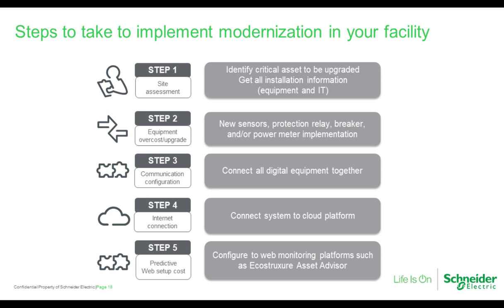Some of the steps to take to implement modernization. When we're looking at implementing thermal sensors, protective relay, breaker, and power meters, there are 5 steps that can help with this process. The first step is to take time to do a proper assessment. Identify critical assets to be upgraded. Get all the installation information, equipment, and IT. Those are always important because we have to look at what should be upgraded, what needs to be upgraded, or even in some cases, what needs to be replaced. Okay, we also need to understand what the critical points are that need to be monitored. Oftentimes, companies may provide assessment services or pre-engineering solutions for this.